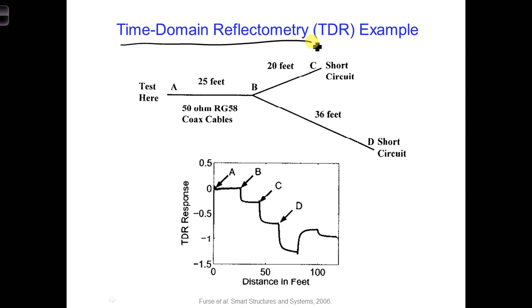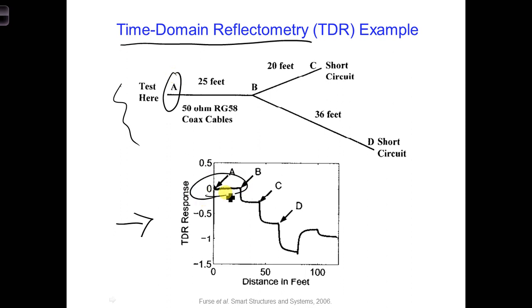From these measurements, TDR plots like the one shown here can be created. This TDR result is for a branched wire network. That network topology is shown on the top of this slide. On the bottom of this slide is the TDR response, which plots the reflection coefficients versus distance down the transmission line. This plot was created from the reflections received at point A, where the reflectometer is located. You'll notice in this TDR example that the reflection coefficient is zero for a while, and when it suddenly changes, they've labeled that as position B, which is where the first impedance discontinuity is located, at the branch point. The reflections from points C and D are also marked.